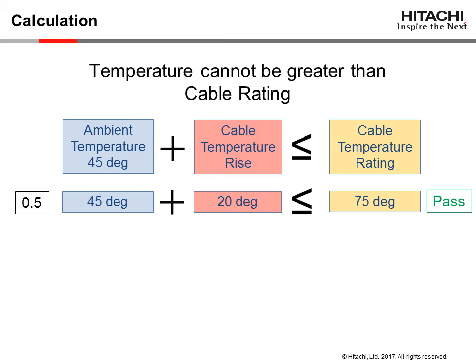Here are two examples of a cable with a maximum operating temperature of 75 degrees. 0.5 amps are applied to each conductor, resulting in a temperature rise of 20 degrees C. Adding the ambient temperature of 45 degrees plus the 20 degrees equals 65 degrees, which is below the 75 degree maximum operating temperature. This is a pass.